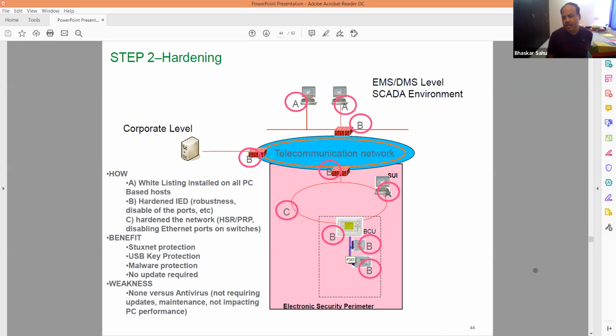...if I give some junk data, instead of behaving properly, the relay will start behaving differently. This is what we call robustness or hardening, where we also disable some ports. For example, if I'm using a 20 port switch but in a substation I'm only using 16 ports, the remaining 4 are vacant, so I disable all those ports. That means even if you manually try to plug in your computer, it will disallow access to the network. This is what we call hardening.